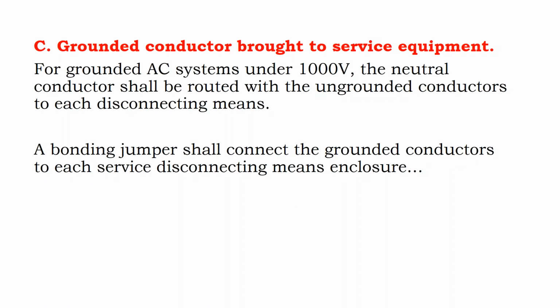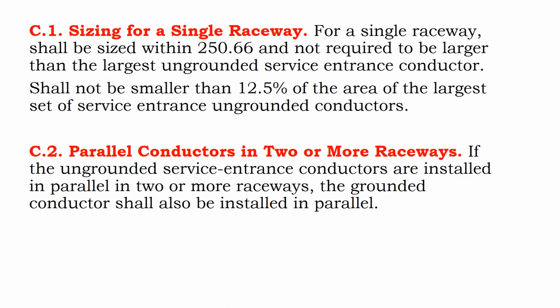The neutral needs to be routed with the ungrounded conductors. So it's not like you're going to have conduit where you have the power lines and then you put the neutral separately. Now, DC systems, you don't have the neutral, and sometimes you have to install a neutral, but it's more for communication than to actually be a neutral. For a single raceway, it shall not be smaller than 12.5% of the area of the largest set of service entrance conductors. I don't know, we'll get into conduit sizing a little bit later.